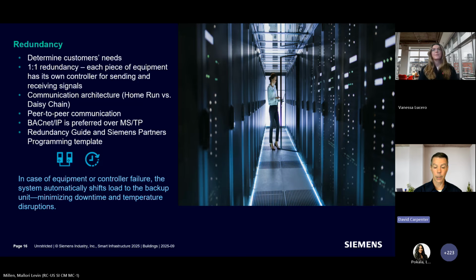Also, our communication architecture with doing IP, even though the Siemens controllers have the ability to daisy chain their IP network, every controller is home run back to a monitored switch. And that way there's no failures that are unexpected in between one panel and another. If there is an interruption to IP, then we're minimizing the places that it could happen.